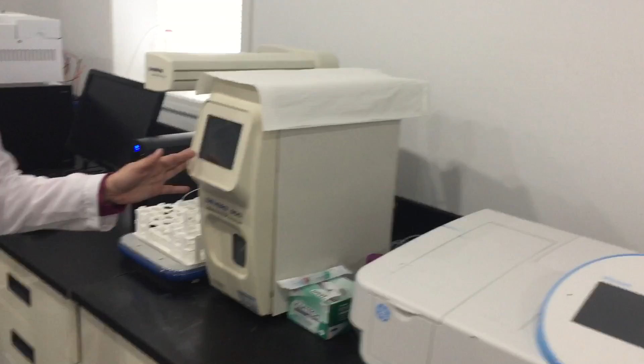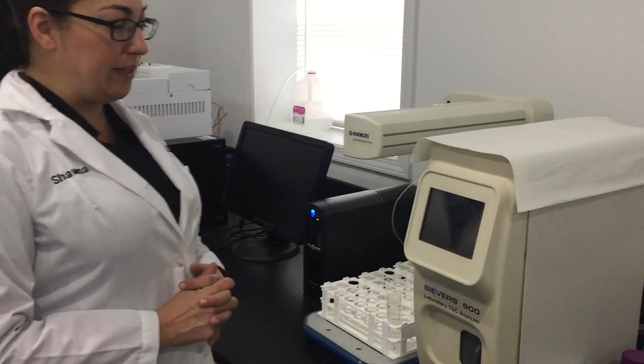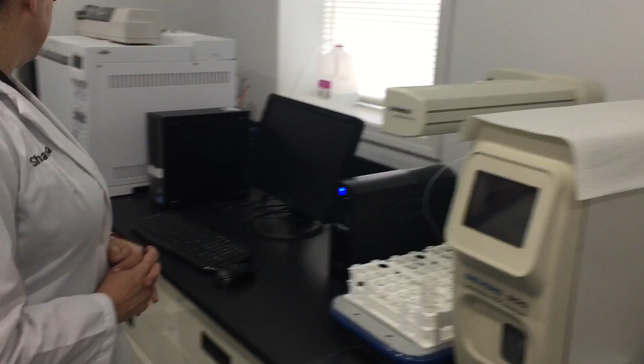This machine is the TOC analyzer. This tells us the water extractable carbon. It will tell us the organic carbon, the inorganic carbon, and the total carbon that is water extractable. We can also use it under other extraction conditions, but for our purposes, we just use water right now. We do have an auto sampler on this unit, so we can load it up and let it run. It is an older unit, but it does the job. It gives us the information that we need.